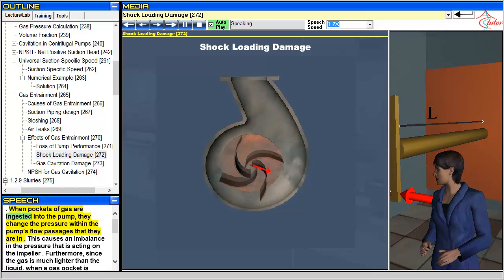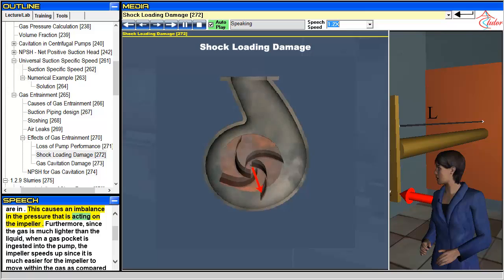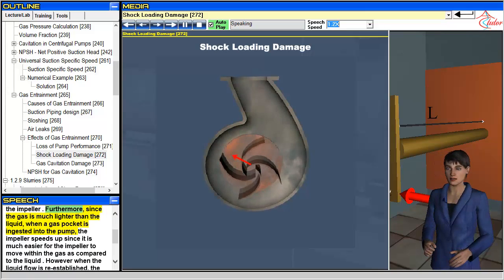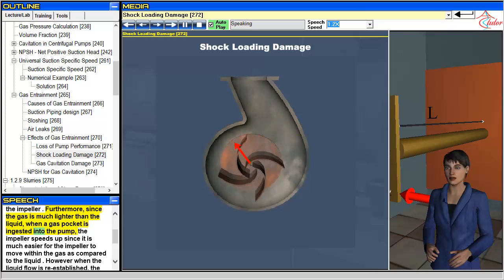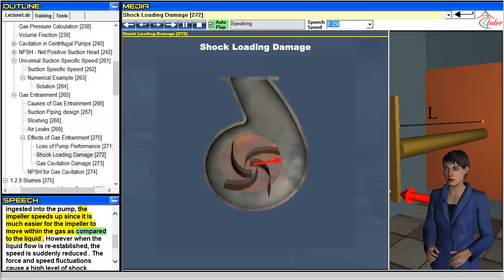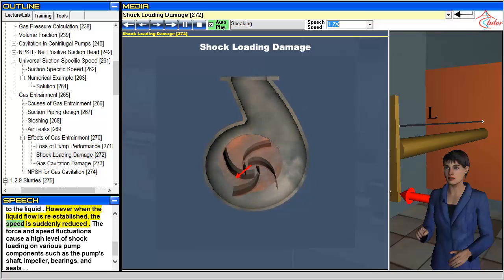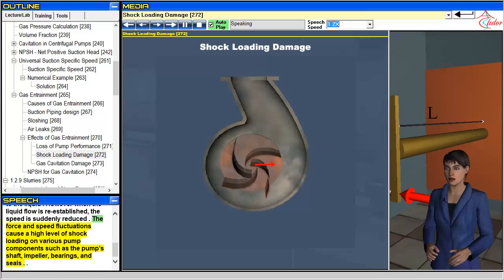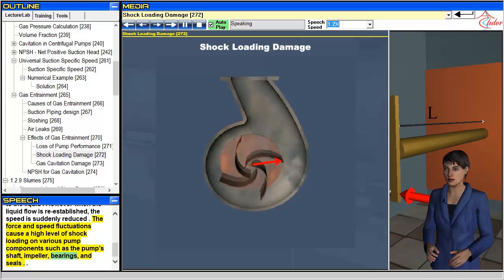When pockets of gas are ingested into the pump, they change the pressure within the pump's flow passages. This causes an imbalance in the pressure that is acting on the impeller. Furthermore, since the gas is much lighter than the liquid, when a gas pocket is ingested into the pump, the impeller speeds up since it is much easier for the impeller to move within the gas as compared to the liquid. However, when the liquid flow is re-established, the speed is suddenly reduced. The force and speed fluctuations cause a high level of shock loading on various pump components such as the pump's shaft, impeller, bearings, and seals.